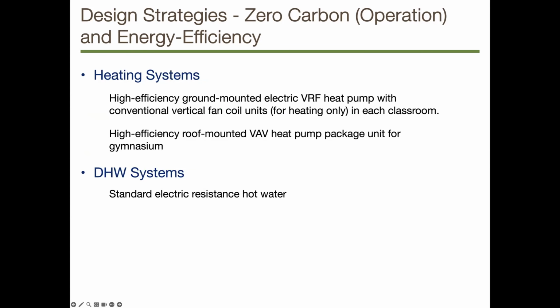The heating system is a ground-mounted electric variable refrigerant flow heat pump with conventional vertical fan coil units in each classroom. By requirement in San Francisco, only heating is provided, no cooling at all in this climate, though they still have a heat pump that could be switched to cooling if they wanted. There's only a roof-mounted heat pump package unit for the gym, the only thing on the roof besides the solar panels that sticks up above the roofline. For cost reasons they went with an electric resistance hot water heater.